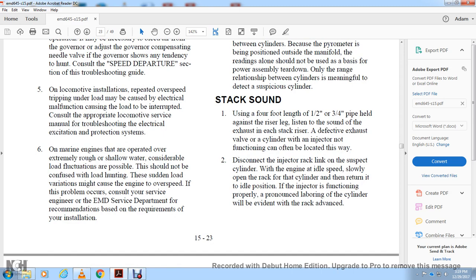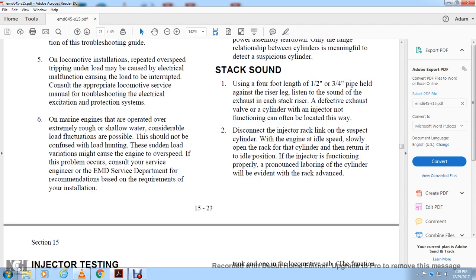On stationary power installations, approximate individual exhaust temperatures using a handheld pyrometer with the engine under load. The reading is useful for comparing cylinder compression because the pyrometer is positioned outside the manifold — readings alone should not be used as the sole basis for power assembly teardown. Only the range of relationship between cylinders is meaningful to detect a suspicious cylinder. For stack sound testing, use a four-foot length of one-half to three-quarter-inch pipe held against the riser with the ear against the exhaust for each stack. A defective exhaust valve, cylinder, or non-functioning injector can often be located this way. Disconnect the injector rack linkage to the suspected cylinder with the engine at idle speed, slowly open the rack and then return it to idle position.